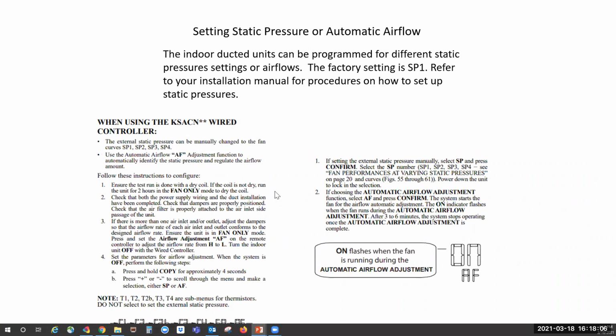Setting static pressure. Static pressure always needs to be set and checked on these. We can do this in several ways. On the 9,000 to 24,000 BTU, we either need to use the wireless remote control or the wired wall controller, and you can go through those settings in the installation manual, and it'll take you through it step by step.